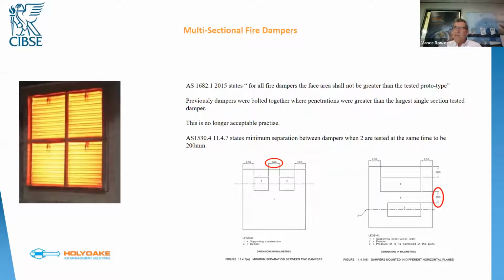Multi-section dampers are definitely something we wanted to cover in a little bit of detail. You'll see there the graphic. That's actually a 2400 by 2400 damper in a test wall down at Warrington's a couple of years ago. And you'll see there that there's a mullion system holding the dampers together. Now, typically prior to 2015, multi-section dampers were actually screwed or bolted together to make up the various ducting sizes that were required, and then installed in the penetration.